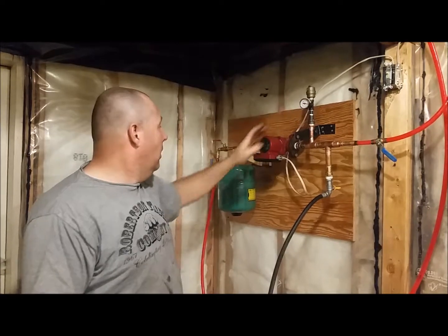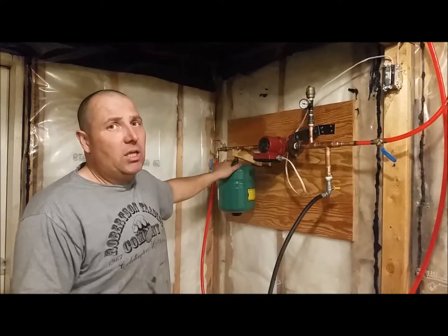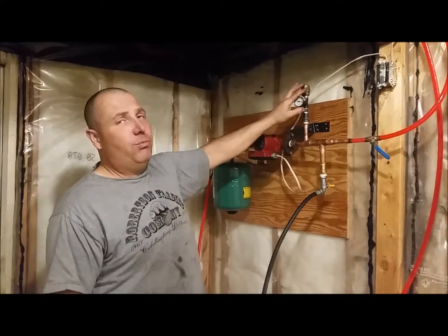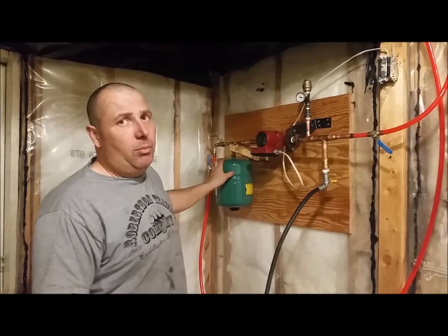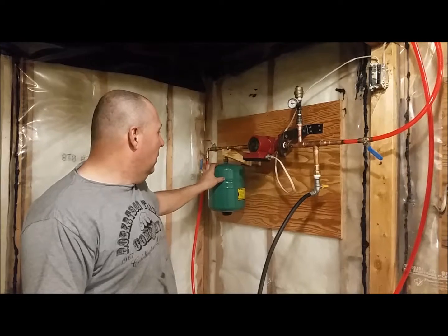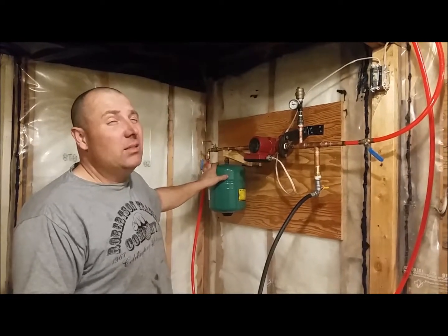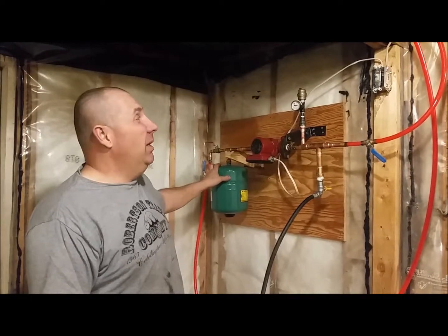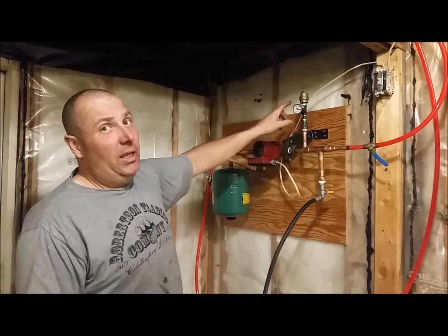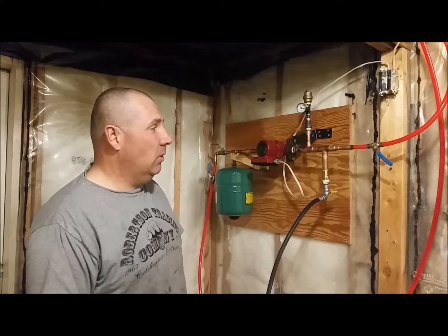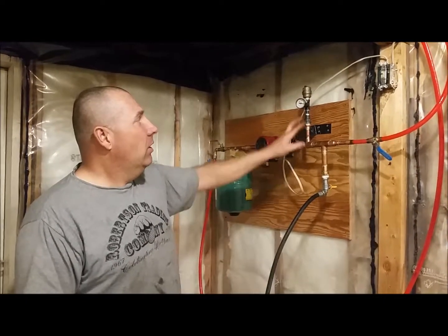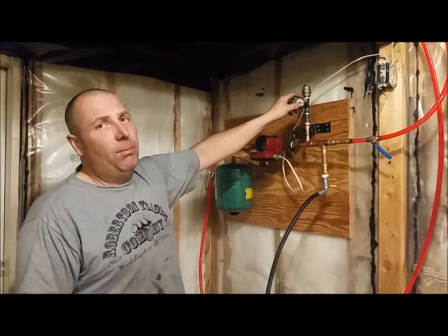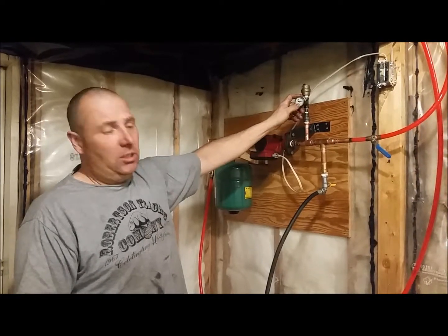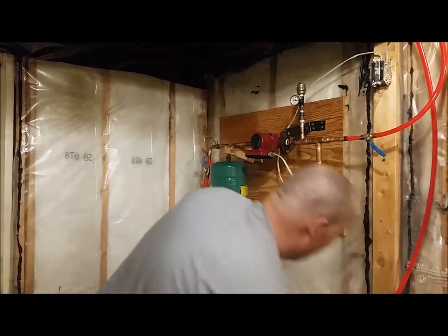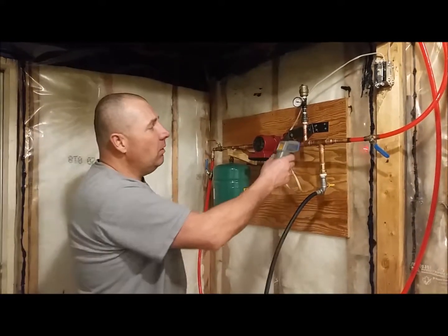We have a fair bit of room. Our expansion tank is set at 12 psi. Once this is at 12 psi, our expansion tank's at equilibrium, and I believe we have up to 16 psi over that. That brings us up to about 28 psi, which on this gauge before the expansion tank is maxed out. So we've got lots of room. It's a very small system. I'm not expecting a whole lot of pressure, maybe a 3 or 4 psi change as the system is heating up. I'll grab the thermal gun. We can shoot some numbers for you on the camera.